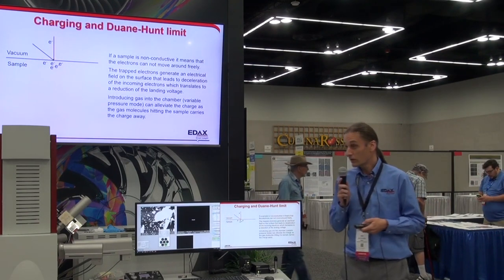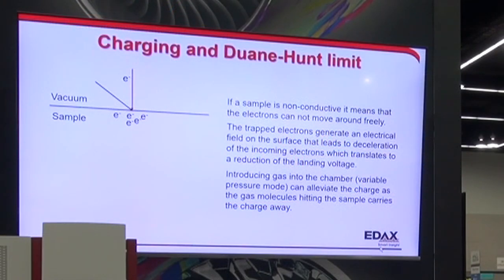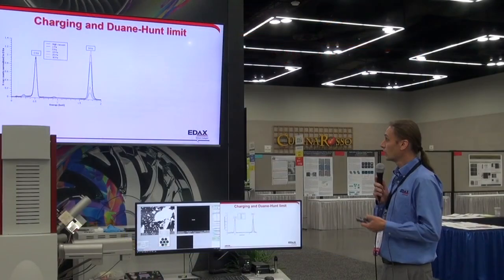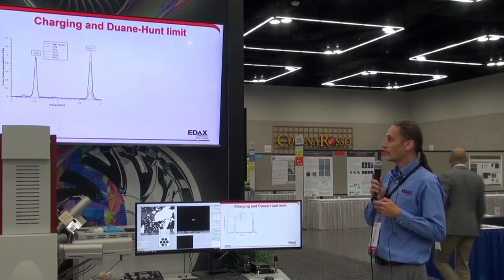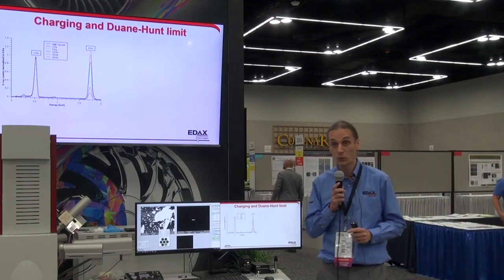One way to get around this is variable pressure mode. If we put the microscope into variable pressure mode, we run a dirty vacuum — bleed a bit of gas in — and gas molecules floating around will hit the sample surface and carry away the charge. So variable pressure is one of the methods we can use to get around charging. The point is that the spectrum and the background will tell us when we have charging and when we do not.